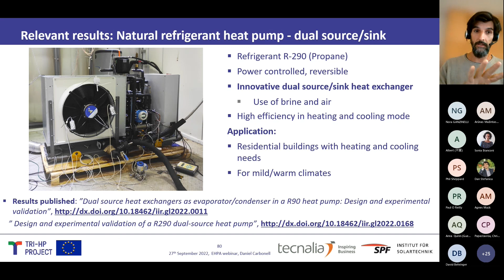Next slide, please. Both systems we've developed have this advanced energy management system, which, as I said before, is a model predictive control. The system does a 24-hour forecast and then decides the best operation condition now. In our simulation framework, we've tested this with our real systems, and we can see that the efficiency and cost reduction—because we're using variable electricity prices—is in the range of 10 to 15%, depending on the system and conditions. This has been shown in simulations.